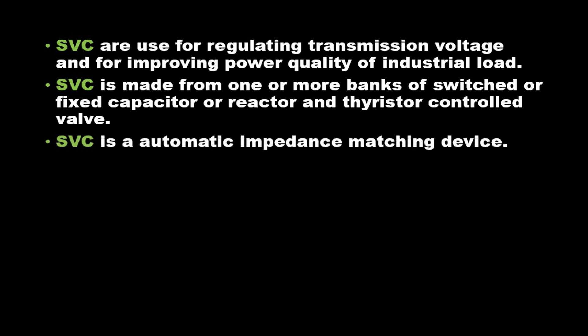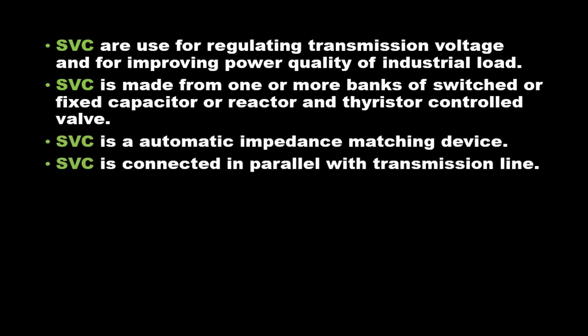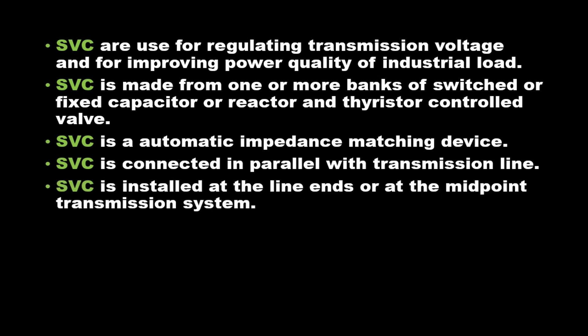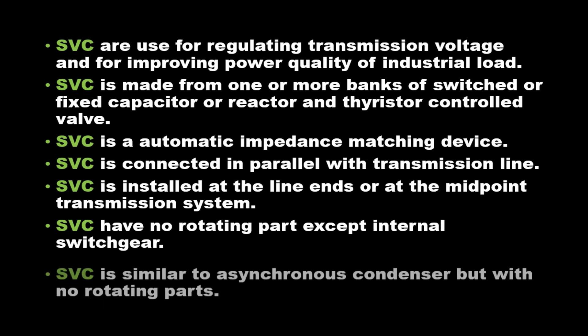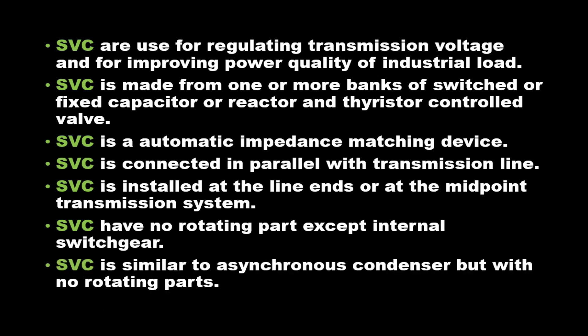SVC is an automatic impedance matching device. SVC is connected in parallel with transmission line. SVC is installed at the line ends or at the midpoint of the transmission system. SVC has no rotating part except internal switchgear. SVC is similar to a synchronous condenser but with no rotating parts.